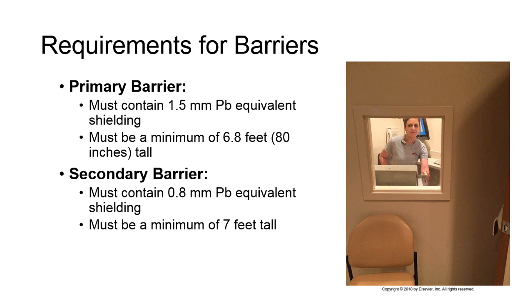Primary barriers must contain shielding effectiveness equivalent to 1.5 mm of pure lead, and must be a minimum of 6.8 feet or 80 inches in height. Secondary barriers must contain shielding effectiveness equivalent to 0.8 mm of pure lead, and must be a minimum of 7 feet in height.